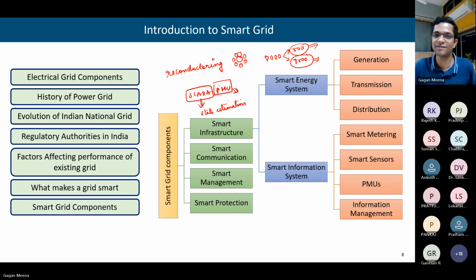The advantage with PMU is that each and every sample is time stamped by a GPS signal. By using GPS, they are time stamping it. That's why we call these phasors synchrophasors. So the phasors are synchronized, time synchronized, and that's why we are able to compare them.